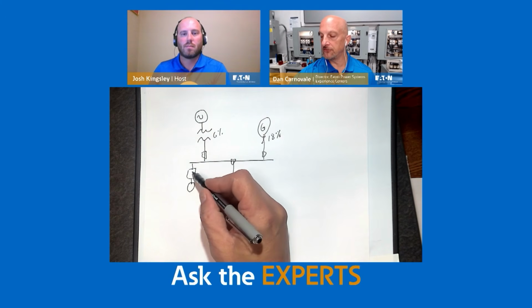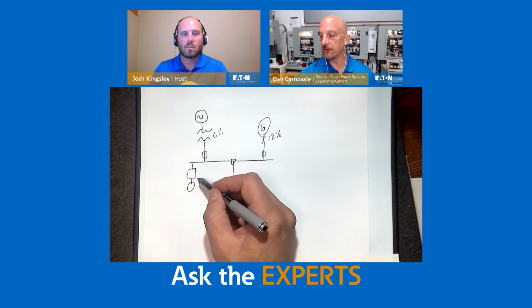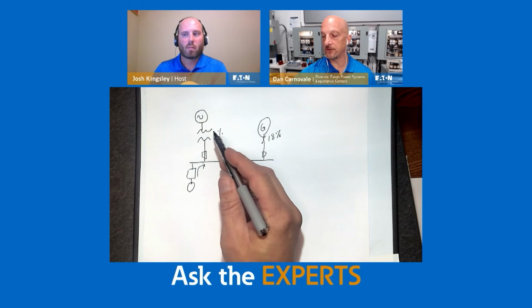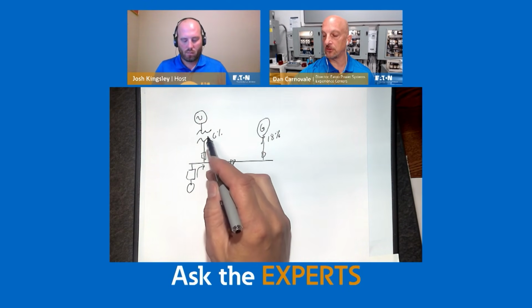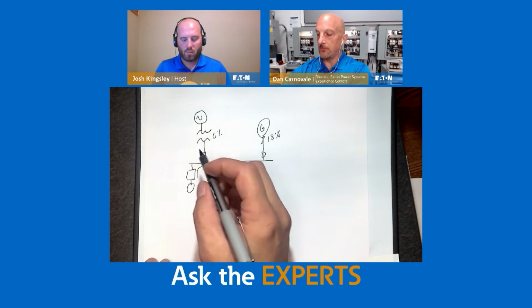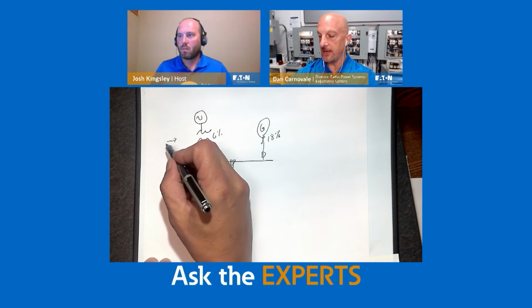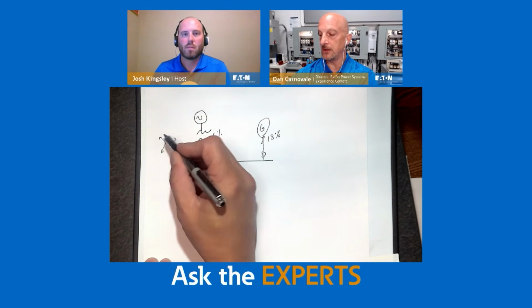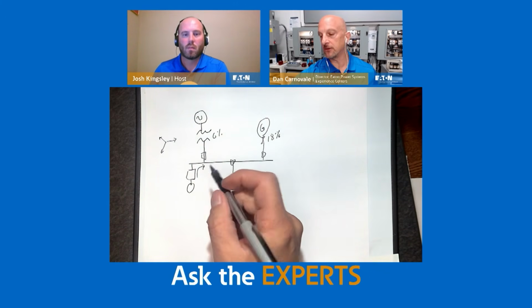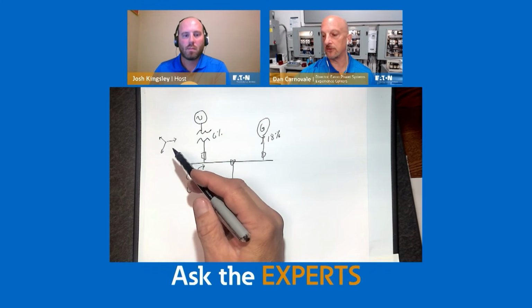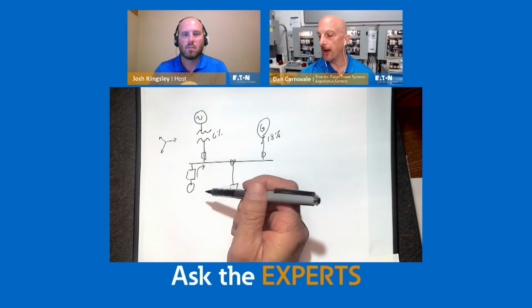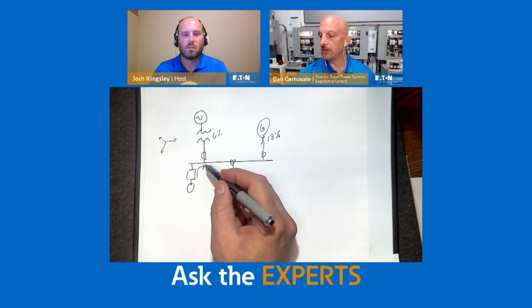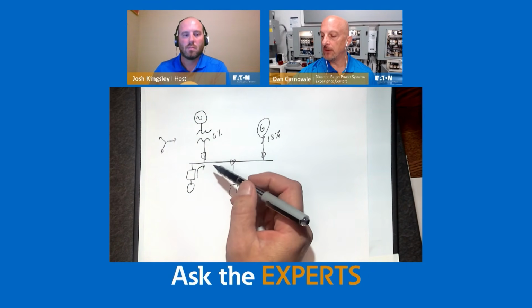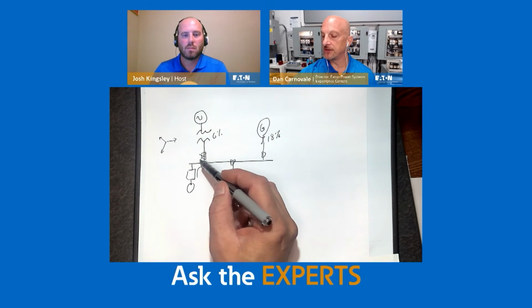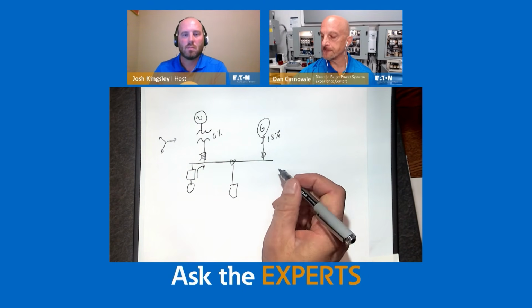But you have all these VFDs or other things that are adding harmonics to the system, and they want to flow back to the path of least impedance. If the generator is offline, that current's going to flow back up to the source. And by the way, it's going to flow out, for example, on A and then back on B and C. A lot of people think harmonics flow to ground, but they don't. They flow out on the phase conductors and back on the other phases or the neutral. But anyway, so as we send the currents out, and then we switch over to the generator, so we take this out and we run over here to the generator.